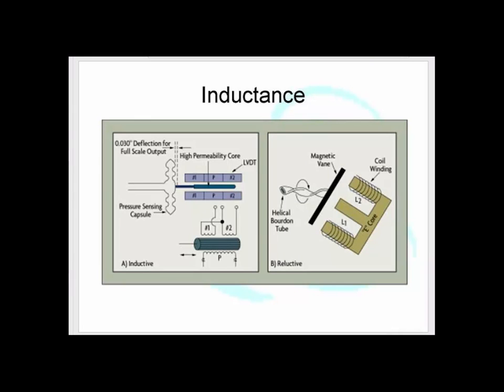Wherever you have capacitance, you always have inductance, because somebody always thinks it's a good idea. For some reason, somebody decided to make an inductance pressure sensor. I wish I had a picture of them. Hopefully you never get to see them apart from in a museum. They are horrible, dreamed up by some nutter on a very bad trip. They've got levers and pulleys and bits you have to adjust. They are just awful. The only thing you need to do if you find one is take it out and put a capacitive one in. That'll be the end of it.